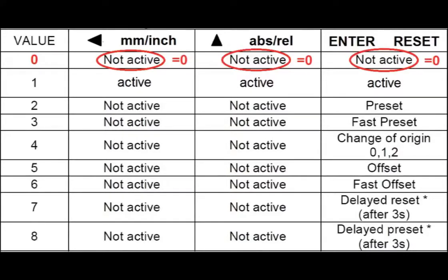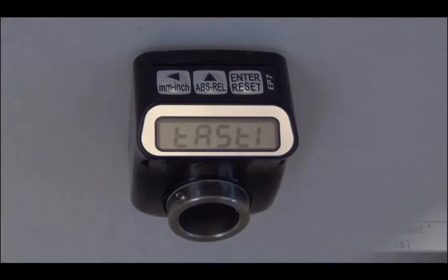For our example, we will disable the reset, the absolute to relative value conversion, and the millimeter to inch conversion buttons in the user mode. The chart shows the required value of zero for each digit in the code for making the keys inactive, so we will enter the code 000.